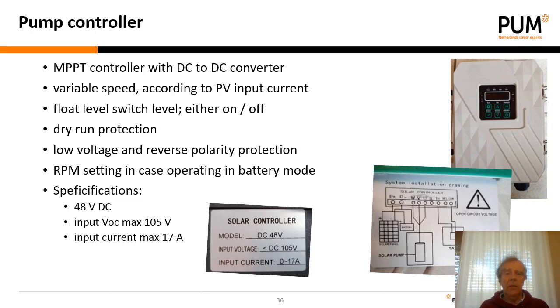And the controller works at 48 DC, input voltage max 105 volts, and input current max 17 amp. And of course the voltage is important, dependent on how many solar panels you put in series. You have to make sure that the peak voltage can never be larger in this setup than 105 volts. And if the setup is such that there is a danger for that, then instead of putting the panels in series, you can put them in parallel.